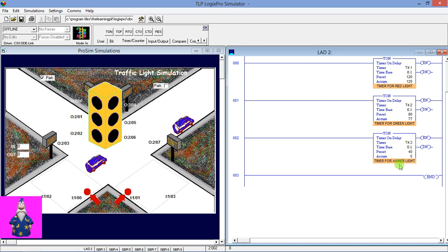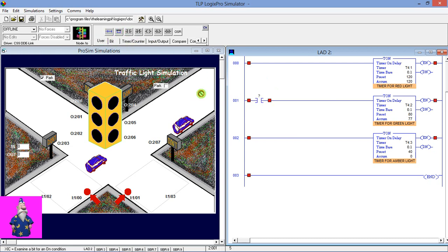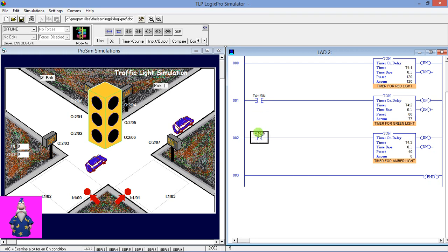We've placed three timers. The done bit of timer one will trigger timer two, and the done bit of timer two will trigger timer three, so we have to use the Examine If Closed instruction of this timer — T4:1/DN, which is the done bit of timer one — and this is the done bit of timer two.